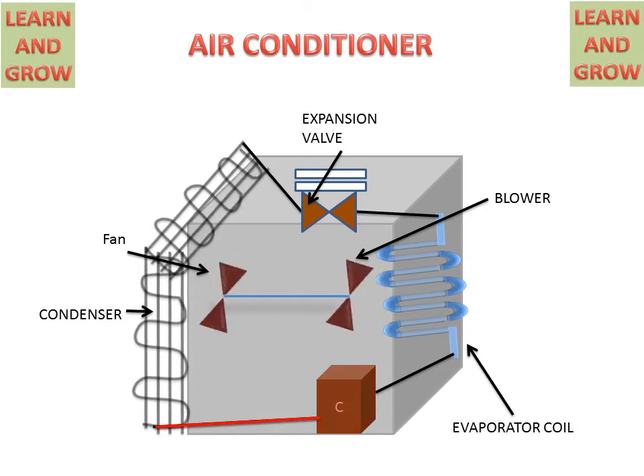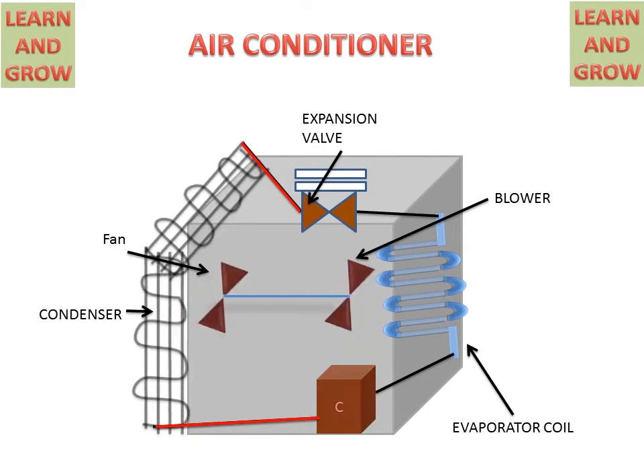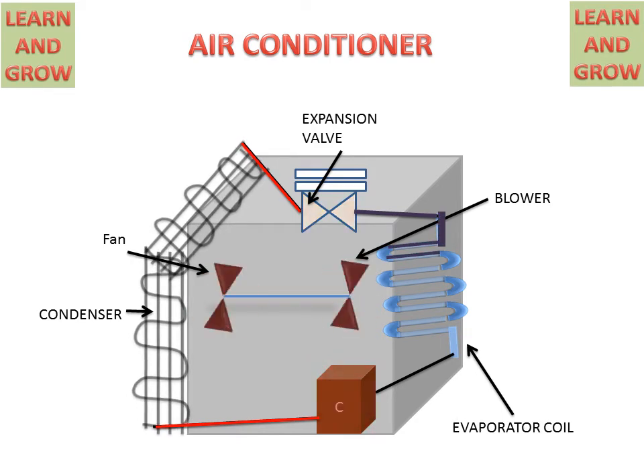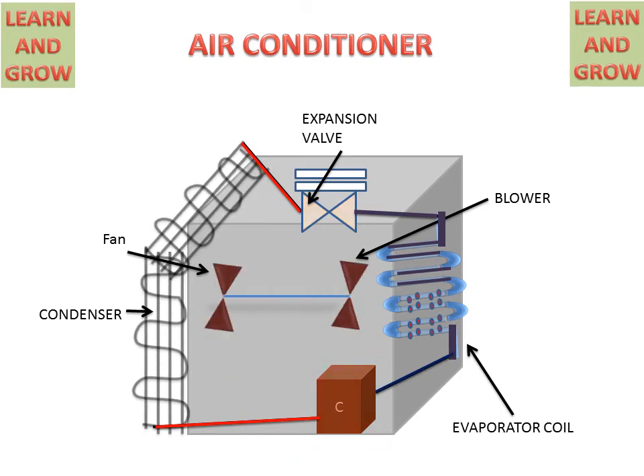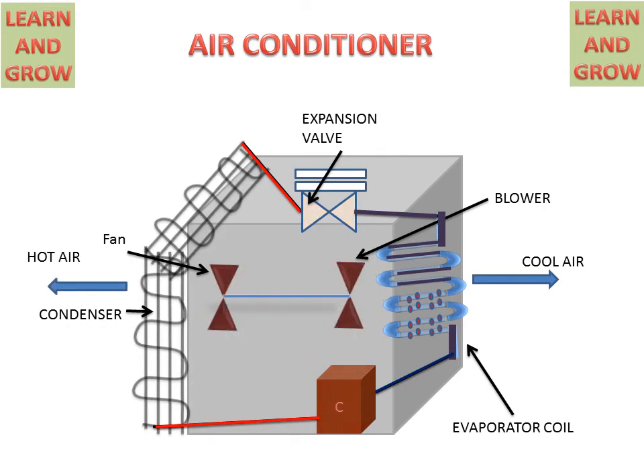This high pressure liquid then goes to the expansion valve, where it is cooled and converted into low pressure liquid. This low pressure liquid goes to the evaporator, where it converts back into vapour and absorbs heat from that space. Cold air comes out from the evaporator coil side, and hot air is expelled outside to the atmosphere. The refrigerant then cycles back to the compressor.